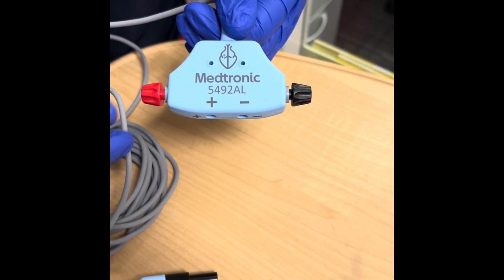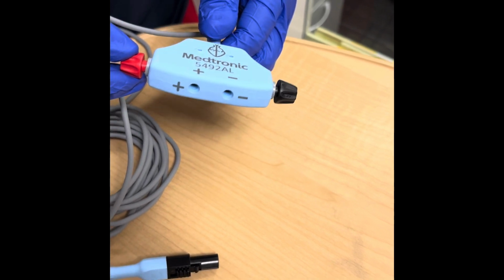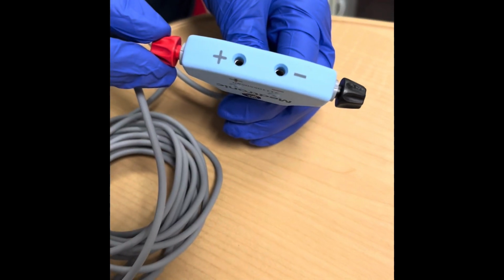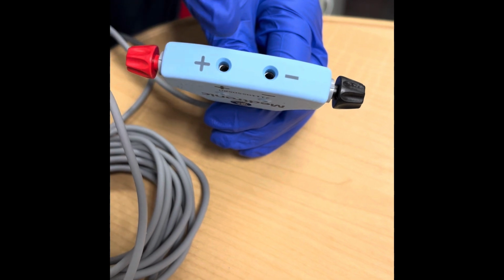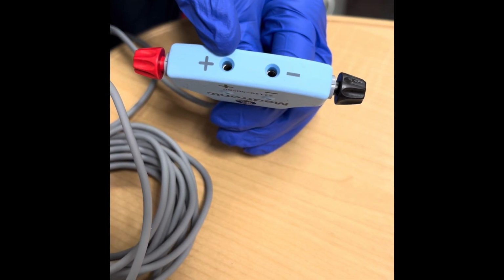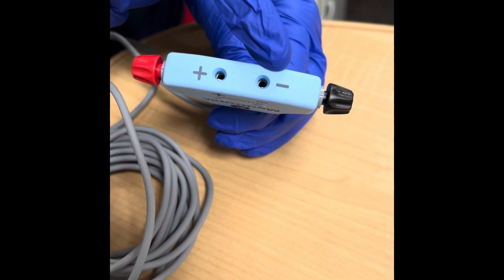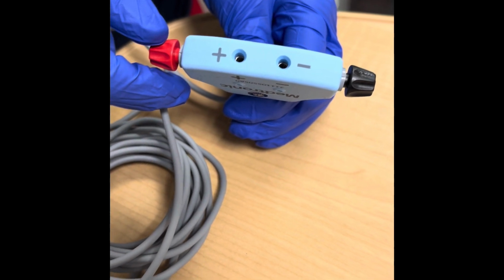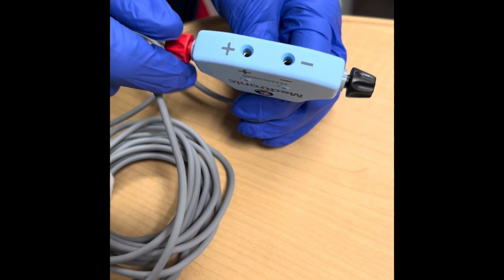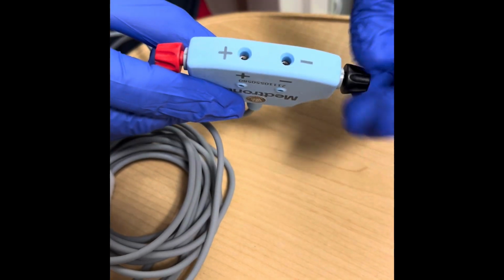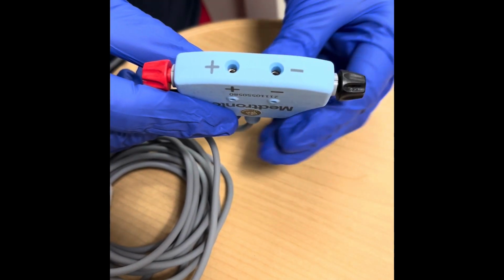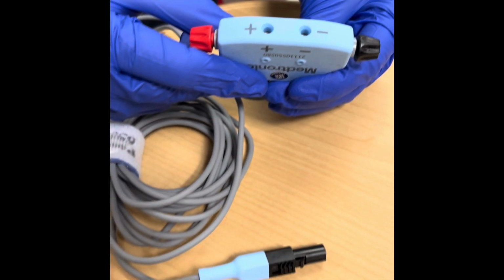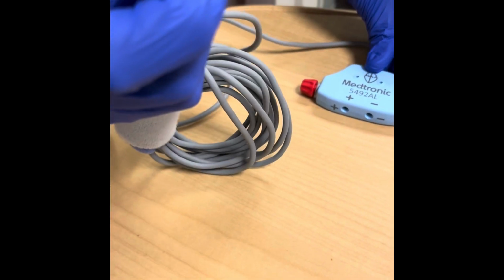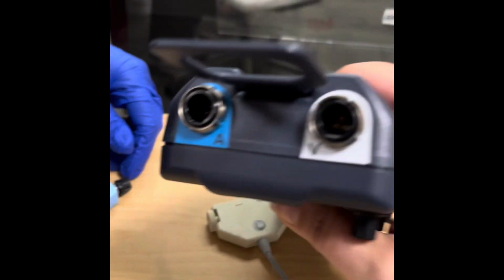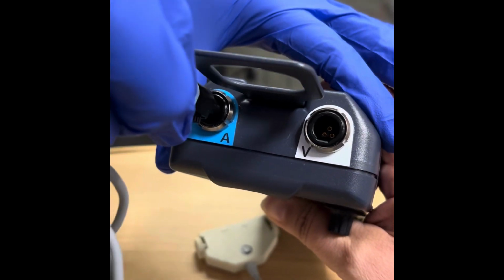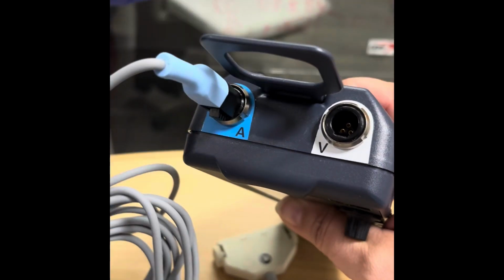So when you take the wires, you will take the caps off the ends, and you will insert each wire into either hole. So it doesn't matter which one it goes into, plus or minus. You're just going to put them in, and then you will tighten each side so that they're locked into place. Then you will take the bottom of your cable and you will plug it into the corresponding spot on the top of your pacemaker, again color-coded with an A, so A for atrial.